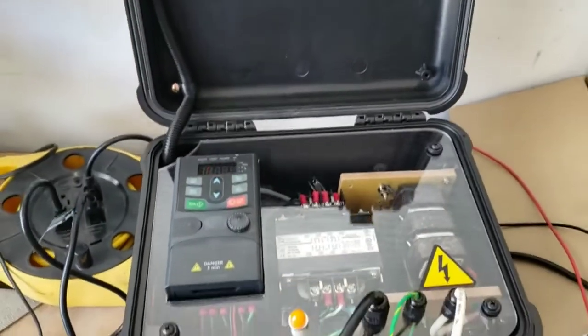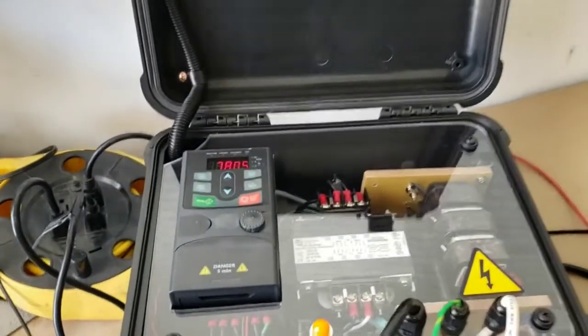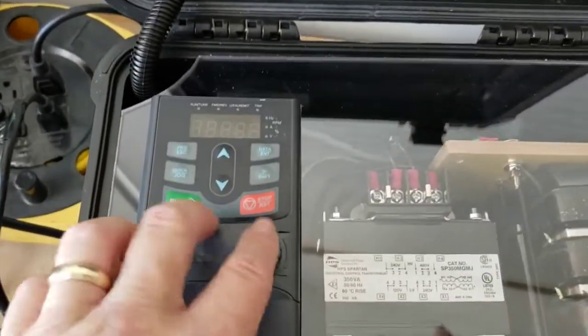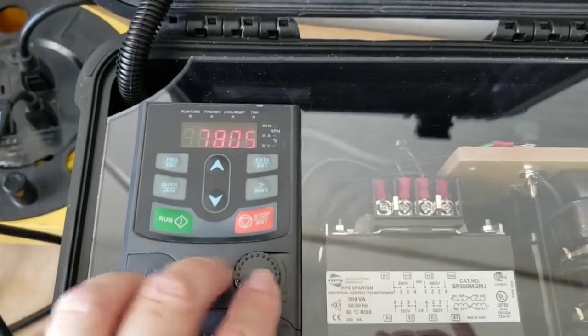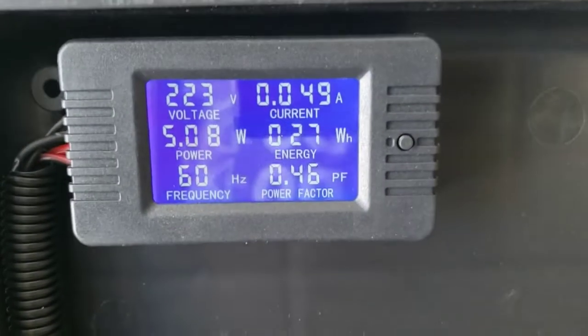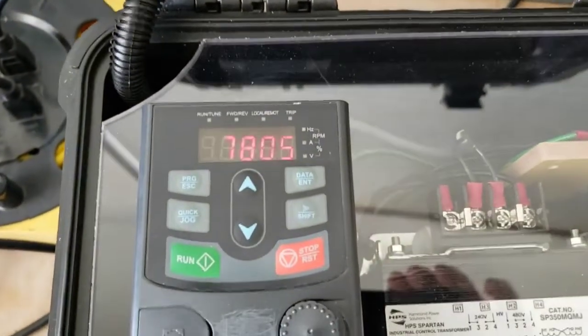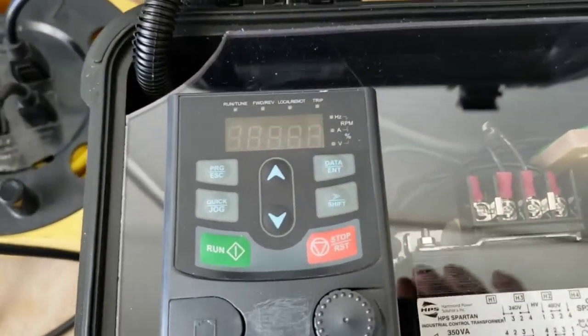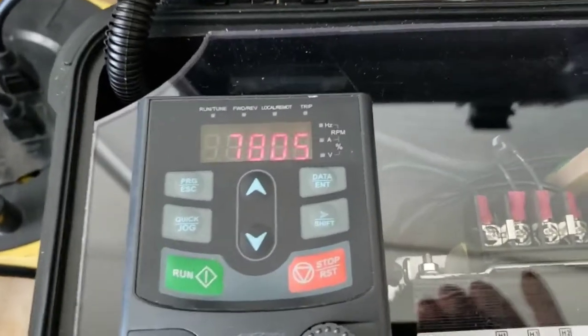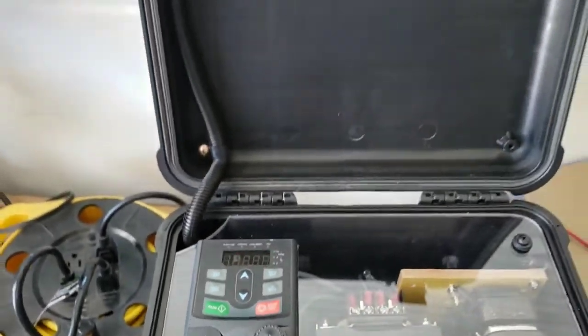So those are two ways to do the test. The normal one, which is usually adequate, is you just turn it on and run up the power and watch to see if you make power and the frequency fall. Test: if wattage does not climb to what is expected, or the frequency falls flat and doesn't go up, it usually goes low frequency on a defective cell generally. That's how you determine a bad cell.